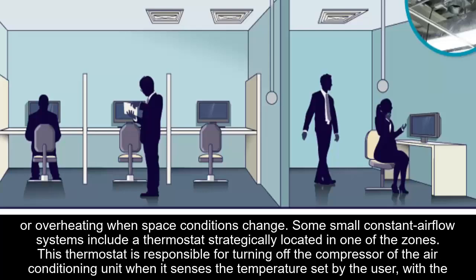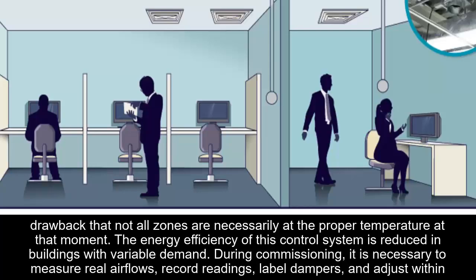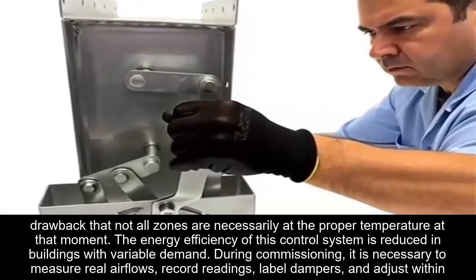This thermostat is responsible for turning off the compressor of the air conditioning unit when it senses the temperature set by the user, with the drawback that not all zones are necessarily at the proper temperature at that moment. The energy efficiency of this control system is reduced in buildings with variable demand.